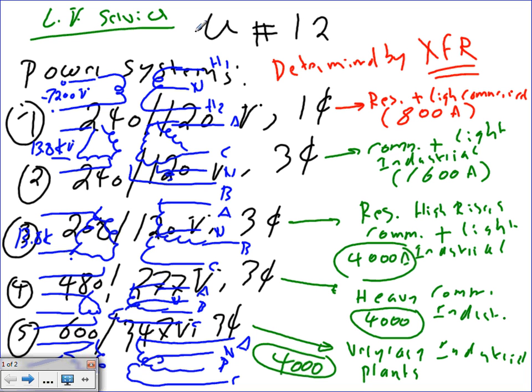Where would I use this service? These are 5 different services that you can get from utilities. Service number 1 can get you a 7200 volt on the primary. You have no control over it. On the secondary side, it gets you a transformer with 2 windings, or center tap transformer, 2 hots, neutral, single phase. You guys are very familiar with this. This is what we did in the residential, 120, 240 single phase. It's mostly residential plus light commercial, and mostly up to 800 amps, though it can go higher than that.